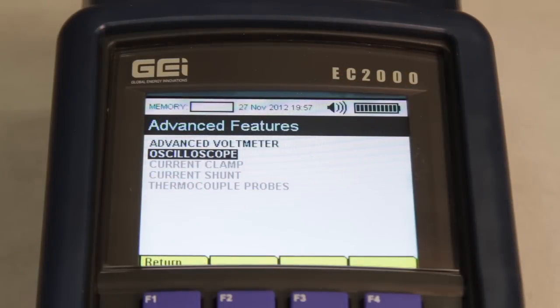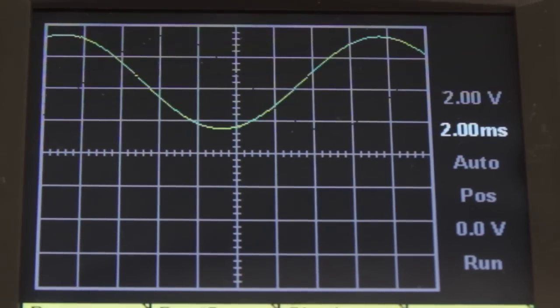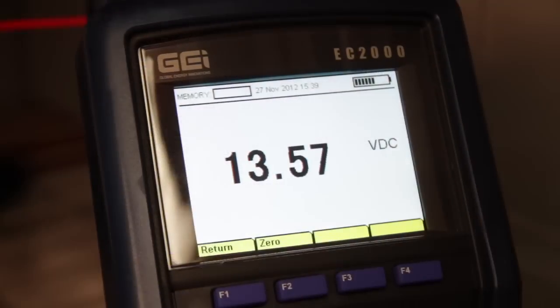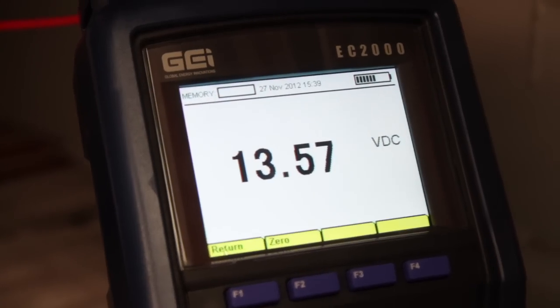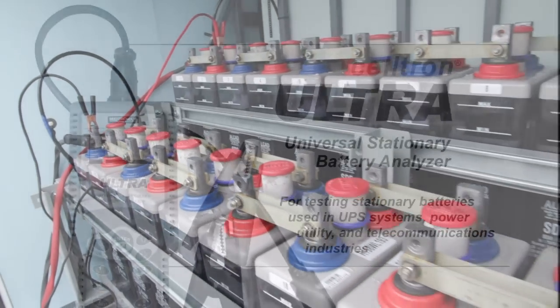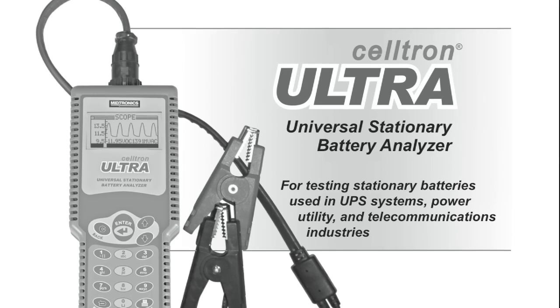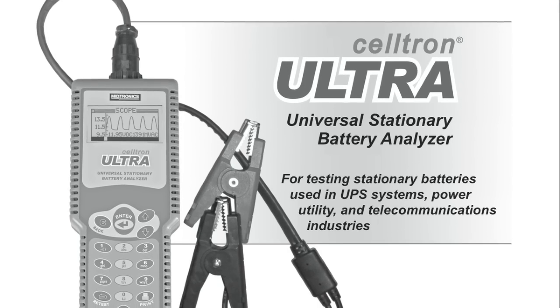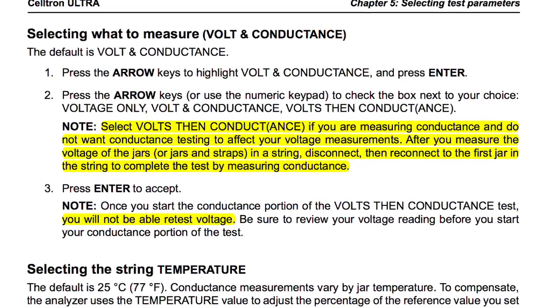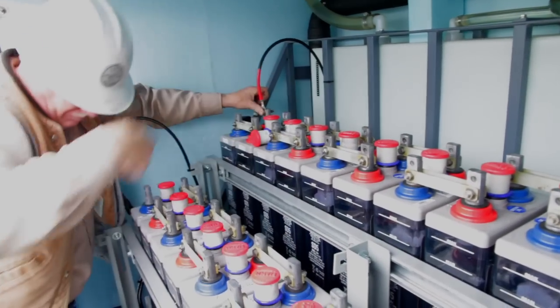AC methods have several advantages. Ideally, they avoid measurement variations that affect DC tests because no charge is added to or removed from the battery. In practice, however, the AC signals produced by some testers may include a DC offset. To minimize the effect of such offsets, the Midtronics Celltron Ultra manual recommends making voltage measurements before conductance measurements. Similar to voltage skewing mentioned earlier, this DC offset can cause variations when performing multiple tests, as is often required when retesting a cell or battery.